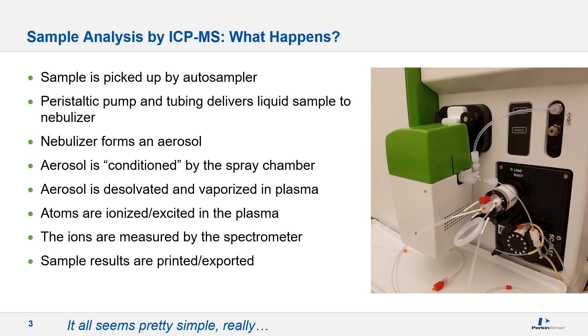Let's review what happens in a typical sample analysis by ICP-MS. First, the sample is picked up by your autosampler. The peristaltic pump and tubing deliver the liquid sample to the nebulizer. The nebulizer forms an aerosol, which is conditioned by the spray chamber. That conditioned aerosol is then desolvated and vaporized in the plasma, where atoms are ionized and excited, and ultimately measured by the spectrometer. Finally, your sample results are printed or exported. It all seems pretty simple, really.